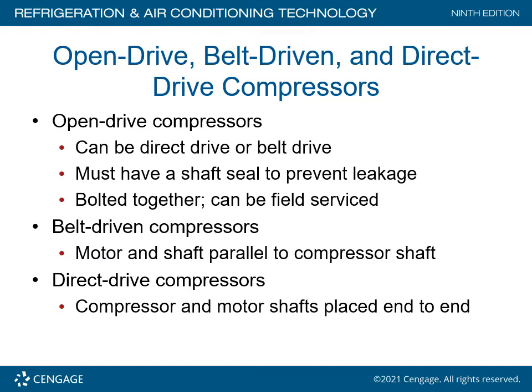Open drive compressors can be direct drive or belt driven. They must have a shaft seal to prevent leakage. When you have a direct drive, alignment of the motor to the compressor is critical — we're only talking about a couple thousandths of an inch. They are bolted together and are field serviceable.